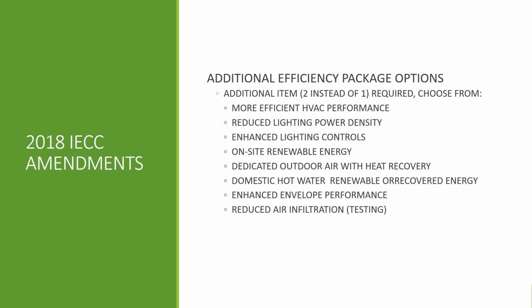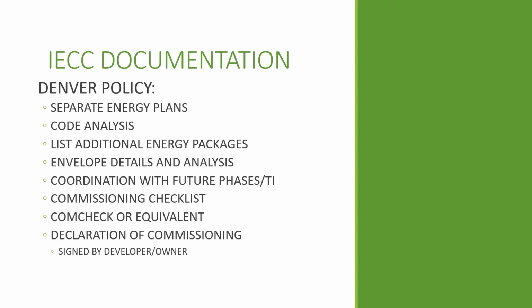On-site renewable energy, you're obviously spending money for that. A DOAS unit - there's certain kinds of systems you probably would do a DOAS unit anyway, dedicated outside air. Domestic hot water, enhanced envelope performance, and reduced air infiltration are also additional ways you can do this. The reduced air infiltration thing you have to meet and test - baseline testing is 0.4 CFM per square foot of exterior envelope, whereas the enhanced is 0.25, and you're going to test and meet that 0.25 CFM per square foot.